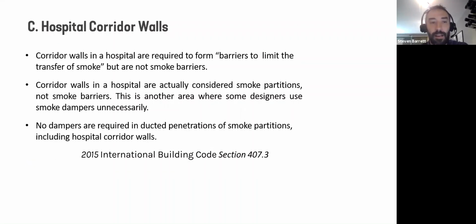And lastly, hospital corridor walls, they're required to limit the transfer of smoke, but they're not smoke barriers. So this is a case that I think is missed quite a bit, where dampers are unnecessarily being provided because they assume that the corridors themselves are smoke barriers, but they're not. They're actually smoke partitions. So typically they're ducted, so they do not require the smoke damper.